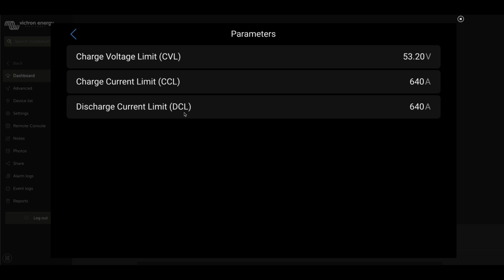Charge current limit and discharge current limit. These are exactly what they sound like. As a battery gets full, you'll see the charge current limit drop. Right now it's wide open. It's in the 80% range. As it approaches 90%, we'll see this in a minute in the advanced tab on VRM. But as it approaches 90%, this charge current limit will start to throttle back as the battery reaches full.